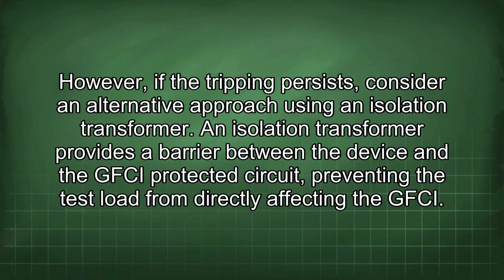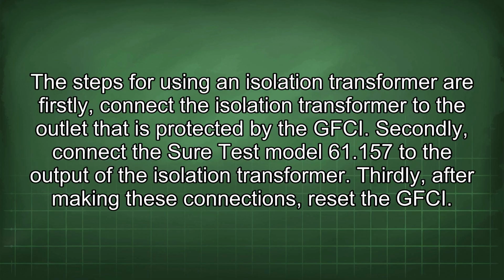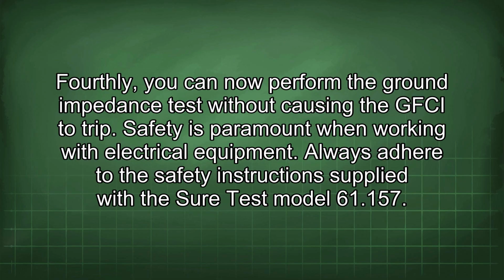affecting the GFCI. The steps for using an isolation transformer are: firstly, connect the isolation transformer to the outlet that is protected by the GFCI. Secondly, connect the Sure Test Model 61.157 to the output of the isolation transformer. Thirdly, after making these connections, reset the GFCI. Fourthly, you can now perform the ground impedance test without causing the GFCI to trip.